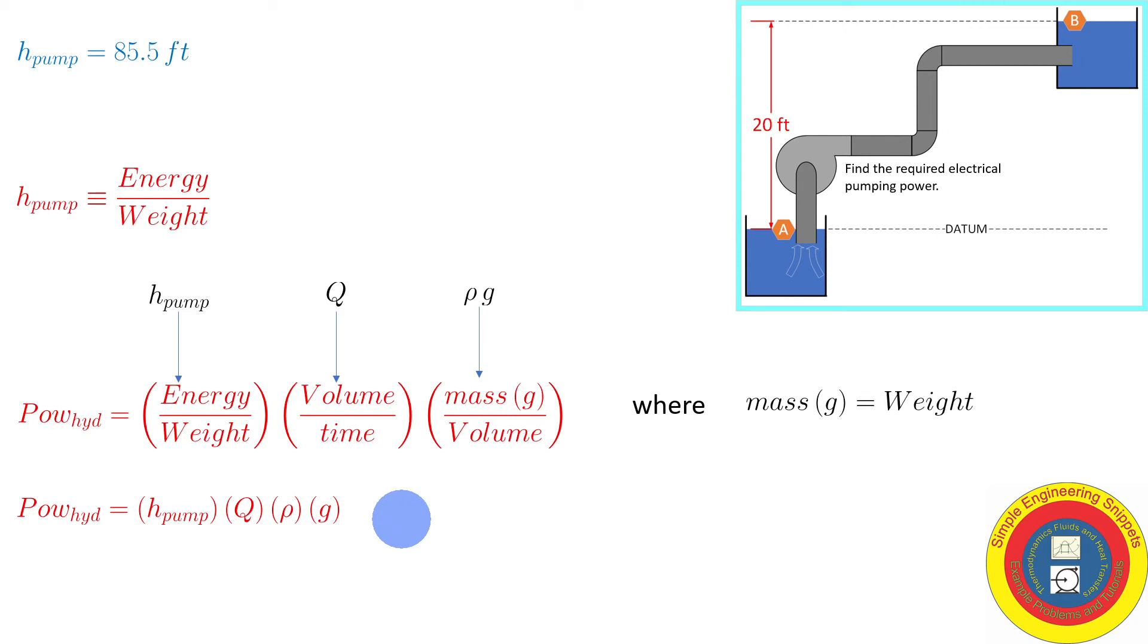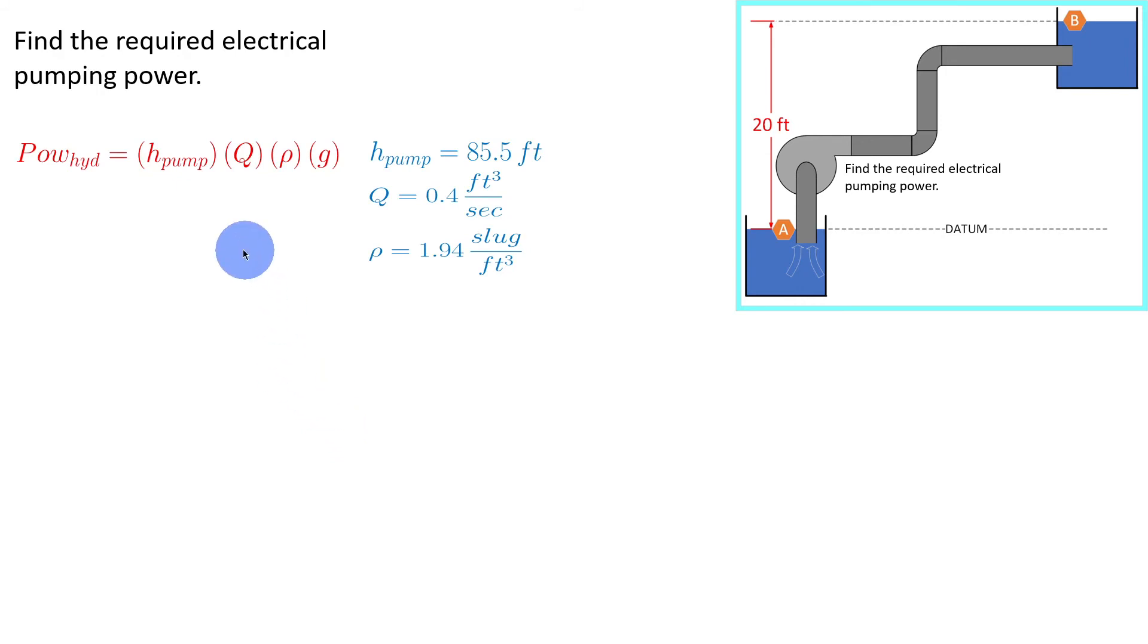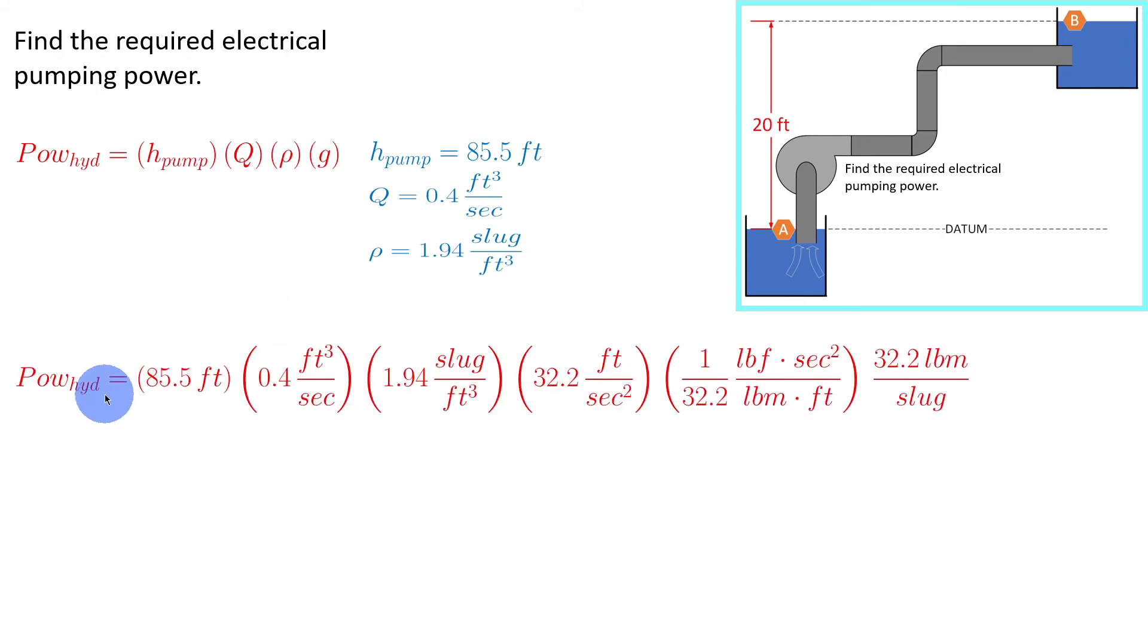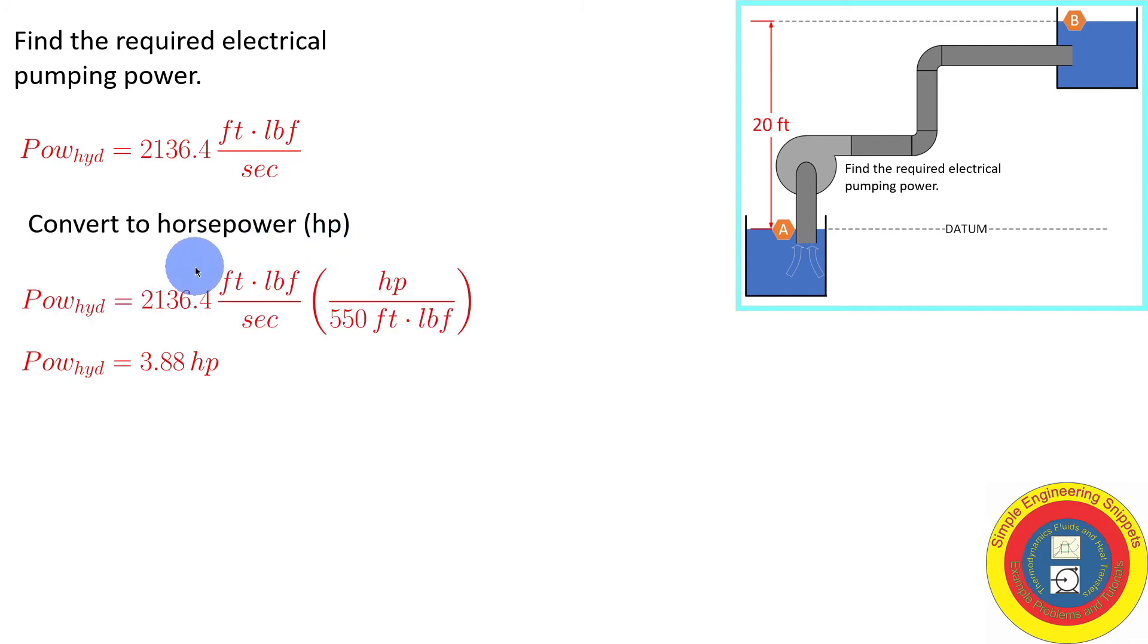Hydraulic power is the energy per time that the pump is adding to the water. This is a fairly straightforward calculation. It's a little messy with dealing with slugs in the G sub C term. But it works out to 2,136.4 foot-pounds force per second. When we deal with pumps, I like to think in terms of horsepower. It comes out to be 3.88 horsepower. That's the hydraulic power, the power that the pump is providing to the fluid.